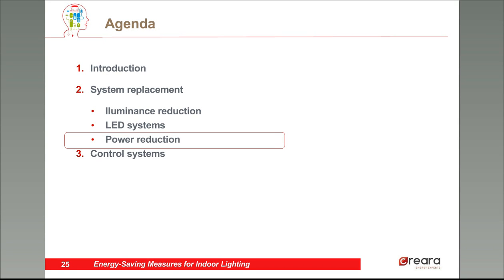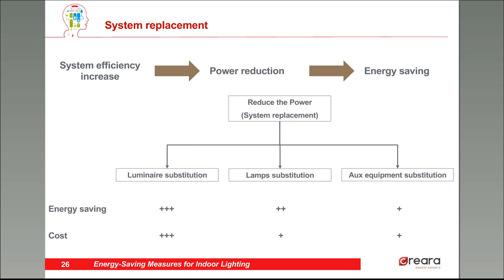Going back to saving possibilities, we talked about illuminance reduction. Now we're going to analyze power reduction by efficiency increase. If the energy efficiency of the system is increased by replacing the luminaire, the lamp, or even the auxiliary equipment, the power and energy consumption are reduced. Replacing the luminaire is more expensive but the energy savings are also bigger. If we substitute the lamp but not the luminaire, we can have some problems with light distribution and heat dissipation. We have to consider that if a luminaire is designed to work with a fluorescent lamp and we change it to a LED, the luminaire performance is worse.